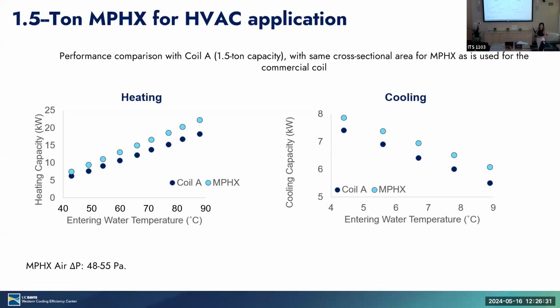The thing is, in traditional heat exchangers you have a bunch of tubes, so if your airflow goes over it, you have cross flow over tubes, creating a wake region, so it's form drag. Here it's more frictional drag because your plates are a little thicker than fins. Fins are maybe 300-400 microns; this is closer to a millimeter. So you have a smaller cross-sectional area for the air to go through, but no wake region. It's a balance between those two that sets up the pressure drop differences.